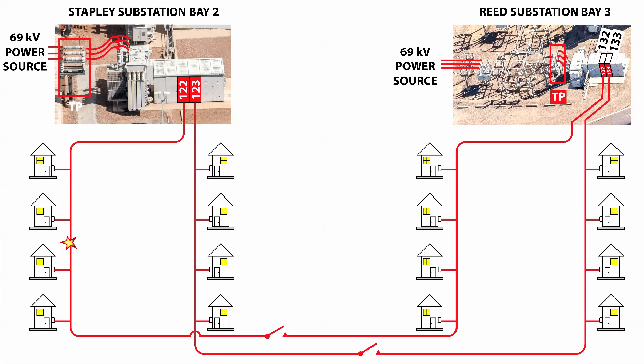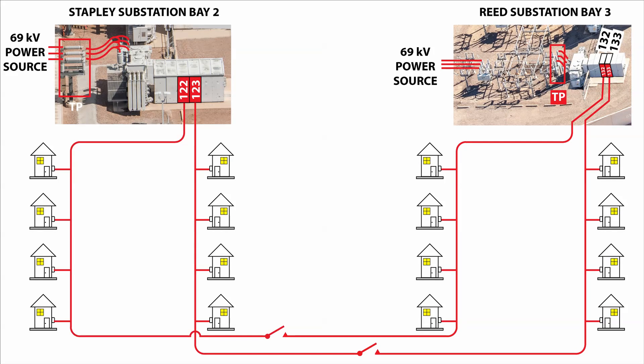If the tree branch is still in contact with the line after the first reclose of the breaker, then the relay will open the circuit breaker a second time, and it will automatically reclose again. Some faults will have cleared prior to the second reclosing, and in this case the breaker will stay closed and customers will barely notice the momentary dimming of their lights. But if the fault condition remains after the second reclosure, then the relays will open the circuit breaker for the third time and this time the breaker will stay open.